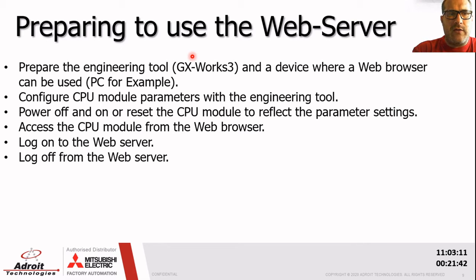You configure the CPU parameters with the engineering tool first, and then you normally power off and on the PLC, or you can reset it. I normally like to reset it, I find it works better than powering it off and on. After resetting, the CPU module will reflect the parameter changes.